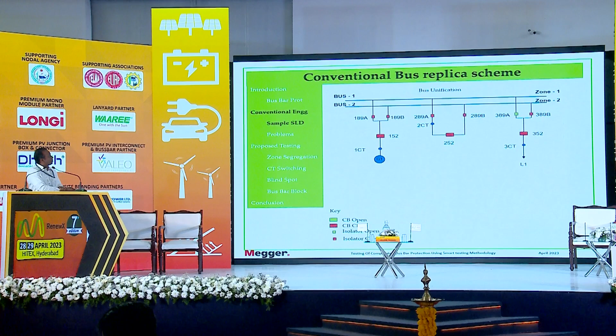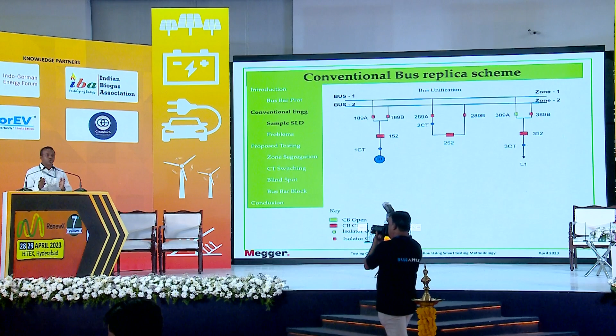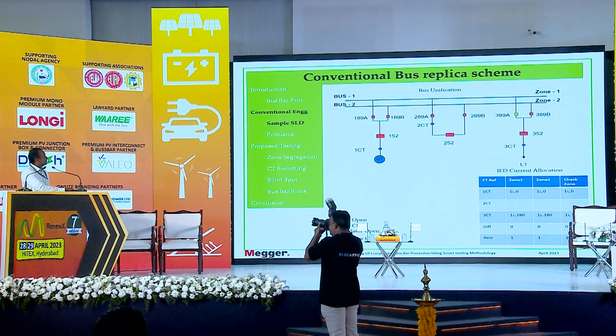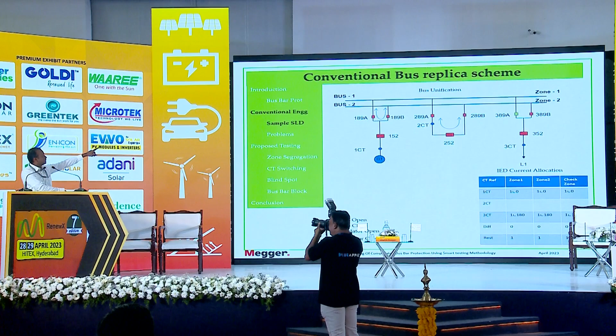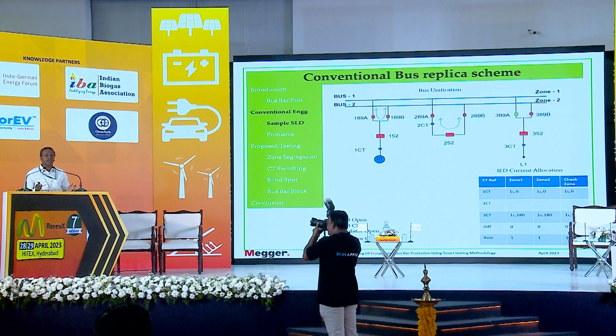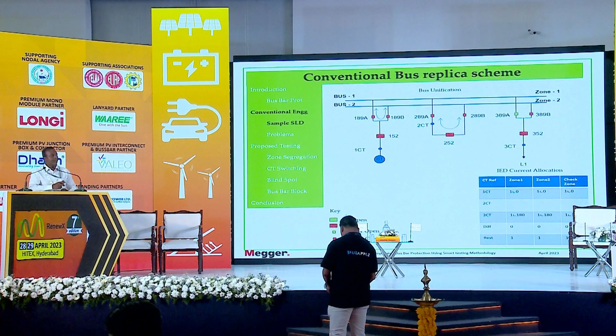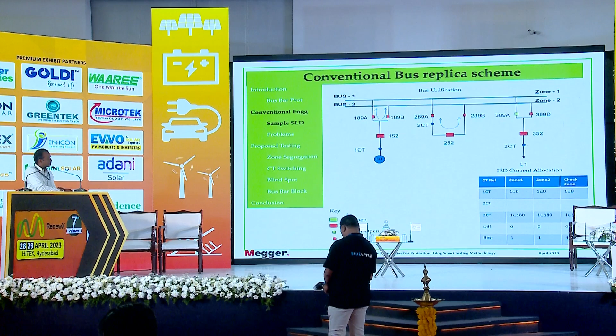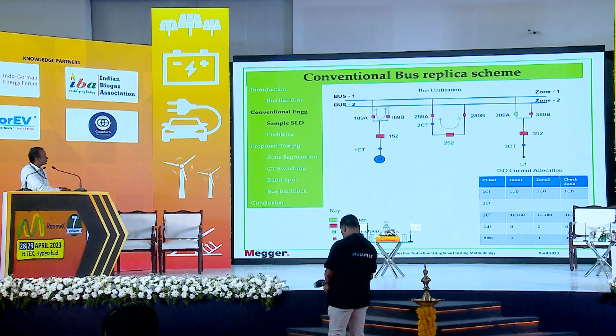Okay, so this is a concept for bus unification. In case we are accidentally closing any one of the bays for 89A as well as 89B, both isolators are closed together, then what happens? We are creating a parallel path to the bus coupler. So that means there is no CT to measure this current. That means the 2 CT current which is measured is actually wrong. So in this kind of situation, we cannot segregate the bus. For any kind of fault, we have to trip the entire bus. So this is called the bus unification concept. So whenever any of the isolators are closed in this manner, we will read all the currents in all the zones. That's the simple logic that we use.